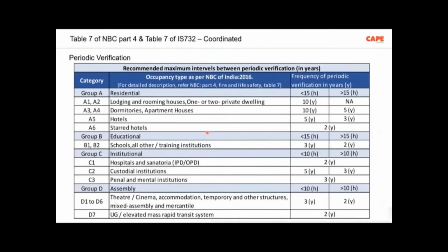There are 2 subjects which influence the building classification. One is what kind of special electrical installations are required in order to handle evacuation during an emergency. And the second one is the frequency of periodic verification. Regulation number 30 says the insulation resistance shall be tested every 5 years, but that is actually applicable for the electricity supply company.